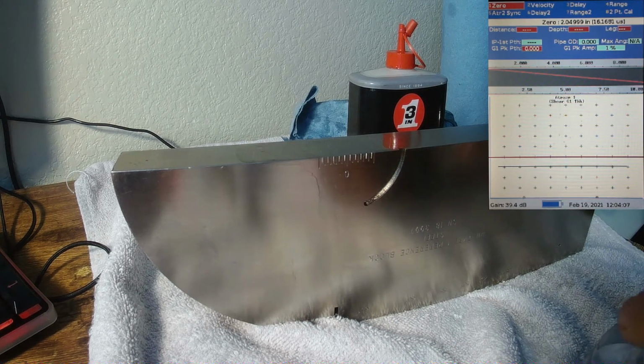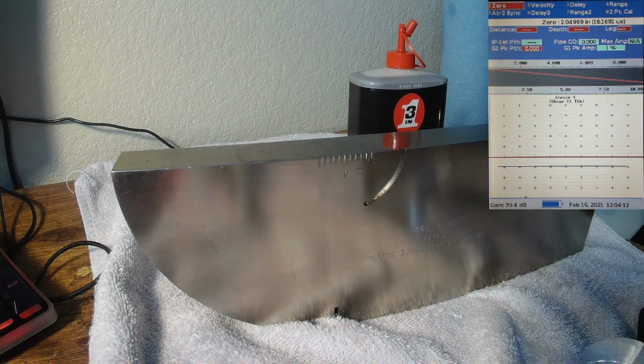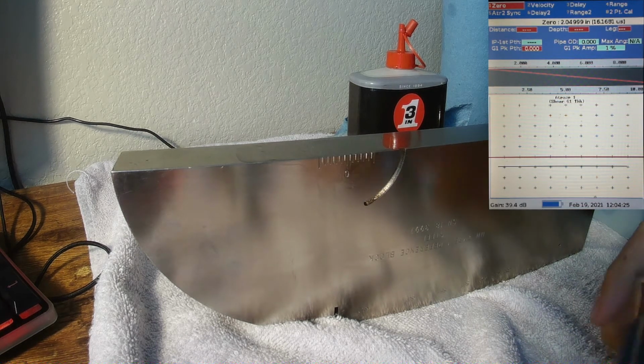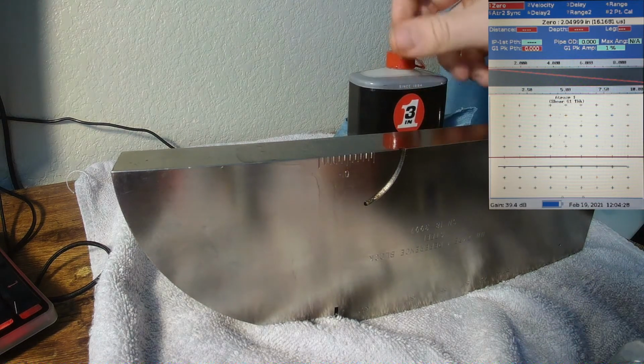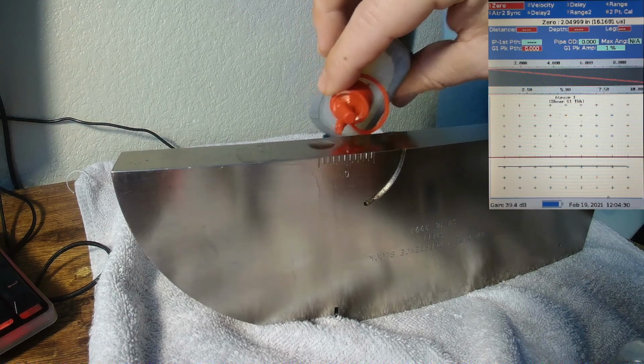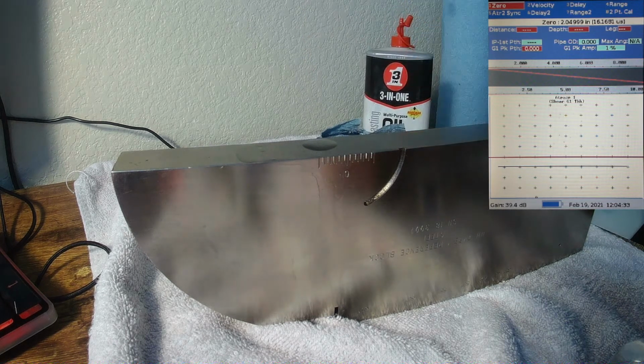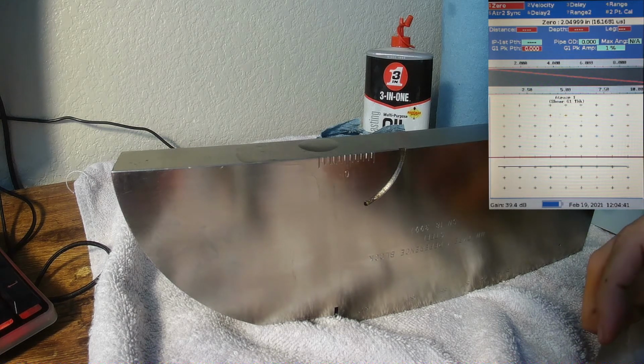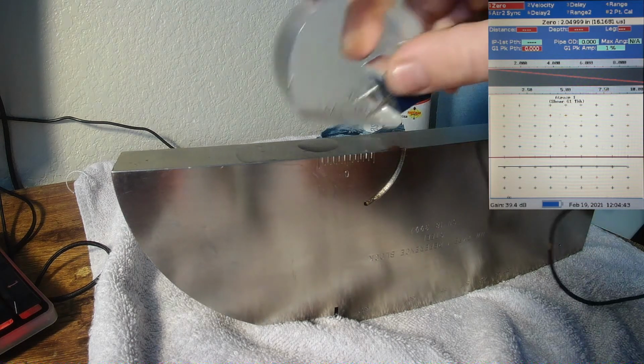All right, so the first thing we're going to do is get our BIP location and set our horizontal linearity. All 4 steps of this are equally important. None of them are more important than the other, but it is important that you do the calibration in this order. Otherwise, you might be off a little bit on some of the later steps if you don't go in order.